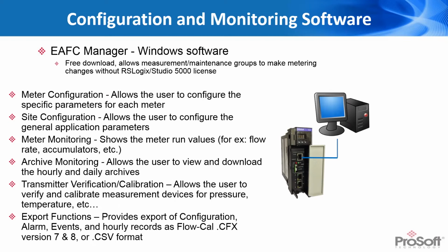And then a key thing that we added about a year ago, year and a half, was the ability to do transmitter verification and calibration. And so as you've got a well pad site with multivariable transmitters out there, being able to calibrate those devices and do verifications on those devices as required through a custody transfer agreement was critical. So we were able to build that into our AFC Manager software so that you could calibrate and verify those devices.